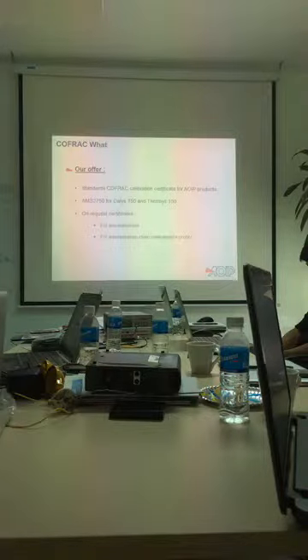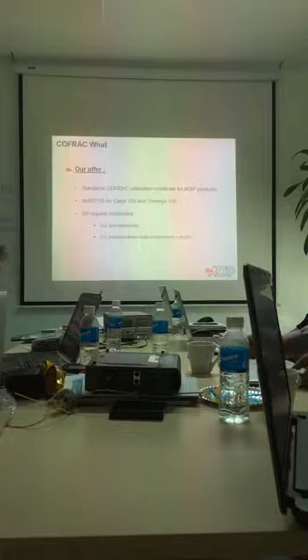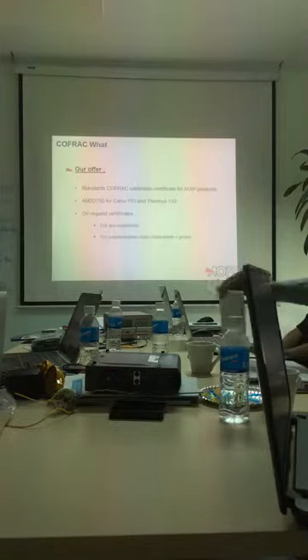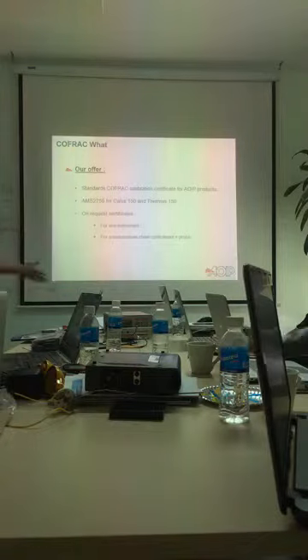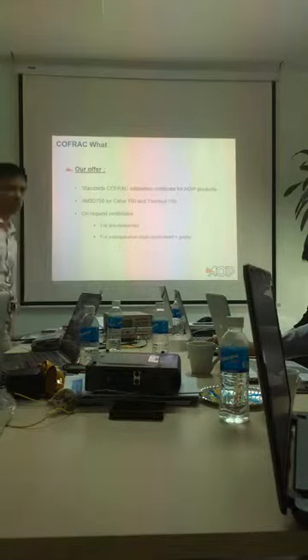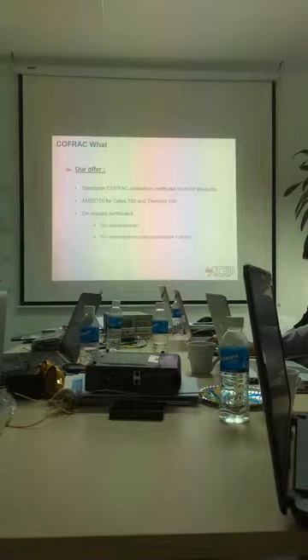So if a customer wants calibration accredited, fine. We don't need to show any type of data. We just want the report, the model name and what test type you have done, okay 1, 2, 3, 4, 5 something. So the client is assured the product already passed the quality control process. We don't have such a document. That is one good point, because that is what the market demands. We can only do conformity certificates, because the list of tests sometimes can be huge.